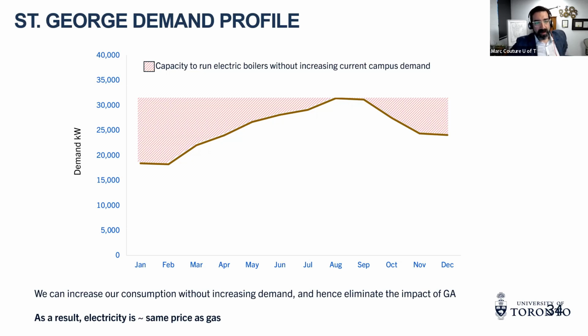So on a month-to-month basis, what we're trying to do is increase the utilization factor of our feeders and the costs we're already paying. Essentially, we're trying to bring our utilization factor closer to 100%. If we already have a peak generated by our existing operations on campus, and we're paying for that peak for the entire month, we can try to maintain that peak and keep it stable all month, leveraging cheaper electricity that's not contributing to an additional peak.